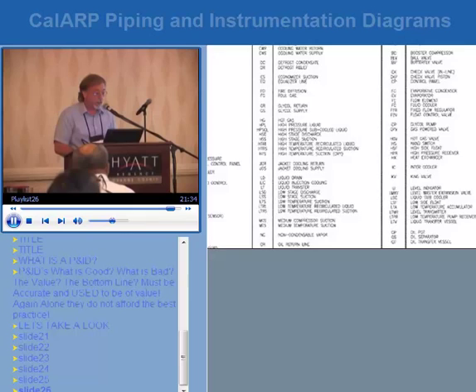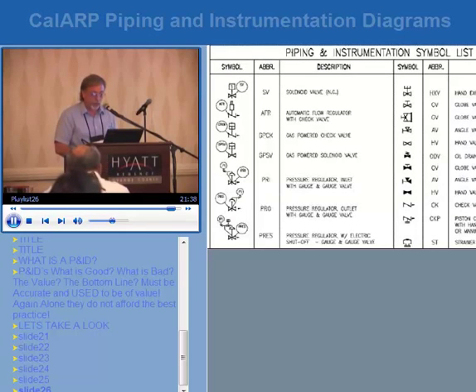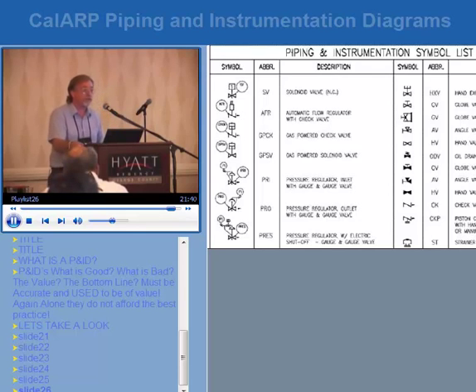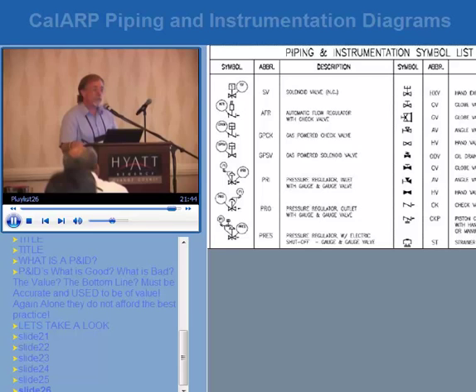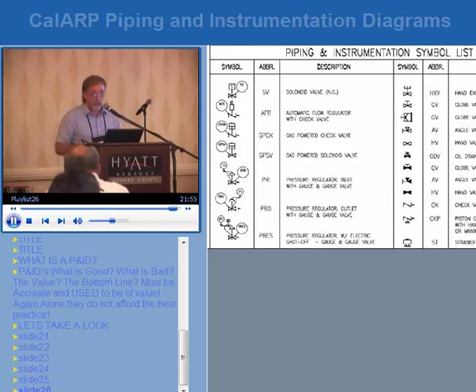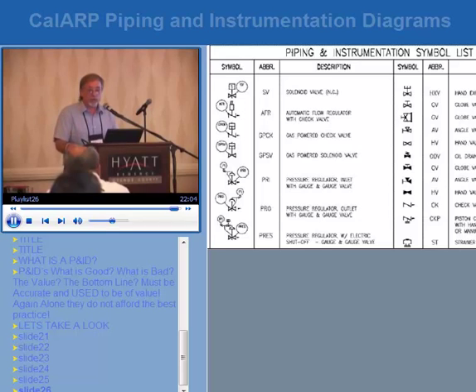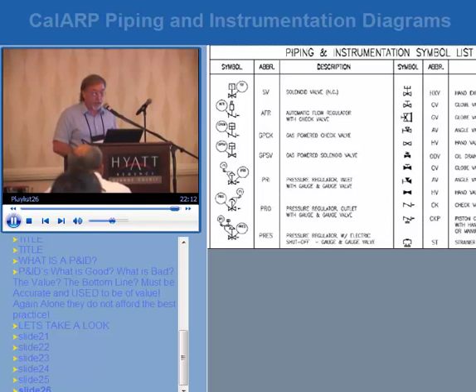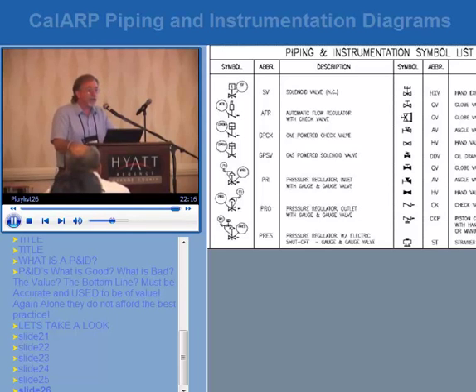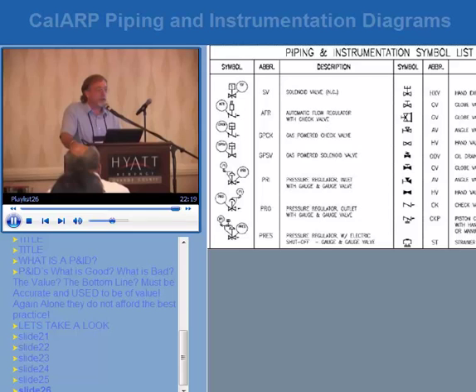Looking at the symbol and abbreviations section: FG stands for foul gas, there's glycol return lines, hot gas, high-pressure liquid, et cetera. There are hundreds of acronyms and abbreviations used — there is no single industry standard but there are many commonalities. It is critical that the operator have the symbol sheet and the proper designations. There are many different types of control valves and they need to be identified on the system so the operator knows the function, direction of flow, and how to manually open or close them.